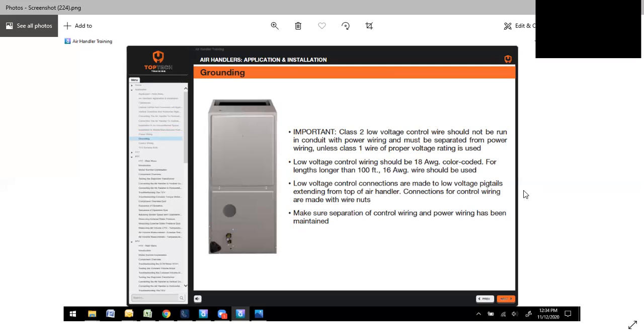Low voltage control connections are made to low voltage pigtails extending from the top of the air handler. They've tried to make it as easy as possible for you. Color-coded, the pigtails to connect to. They made it fairly simple. Connections for control wiring are to be made with wire nuts. Make sure separation of control wiring and power wiring has been maintained.